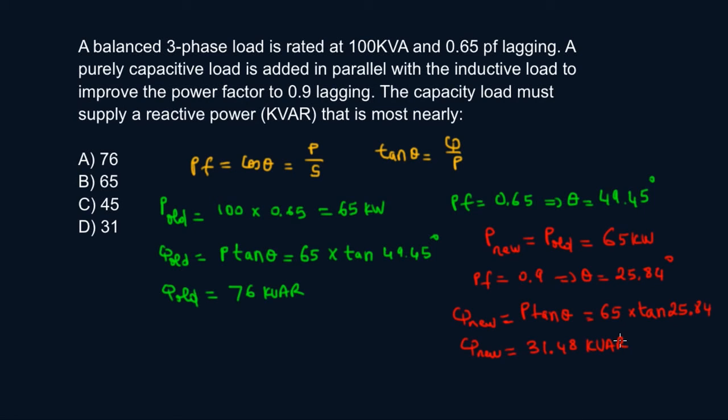So after I added my capacitor, capacitors, they reduce the total reactive power. So after I added the capacitor, my new reactive power total for the entire system becomes 31.48. So I went from a 76 to a 31.48. So how much is the capacitor actually contributing to it? So of course you do the difference between those two. So the reactive power from the capacitor would be 76 minus 31.48. So this is 44.5.